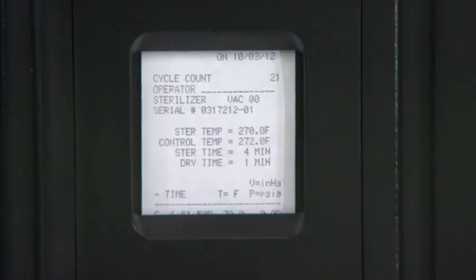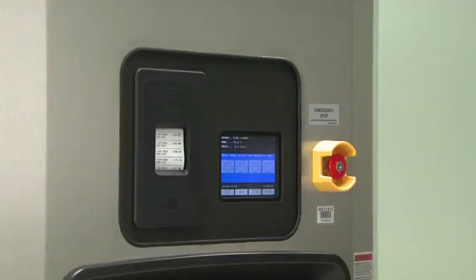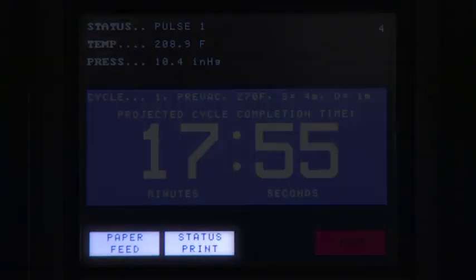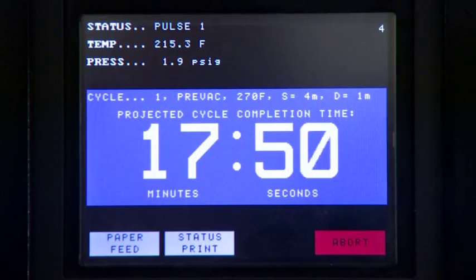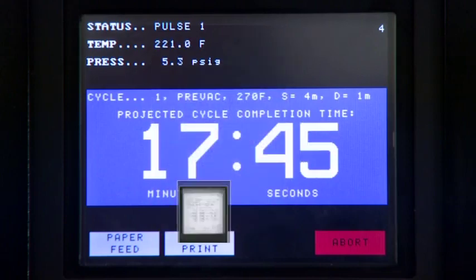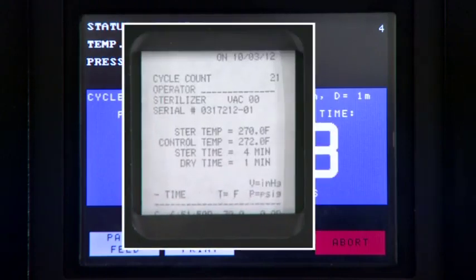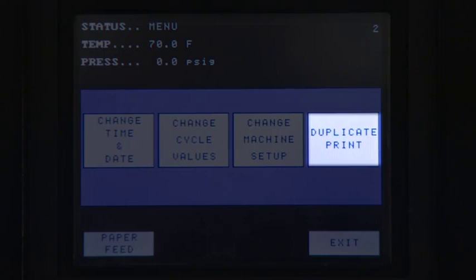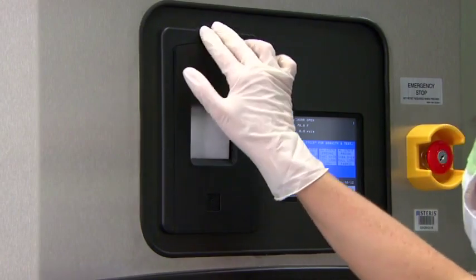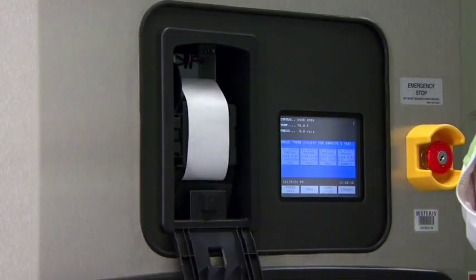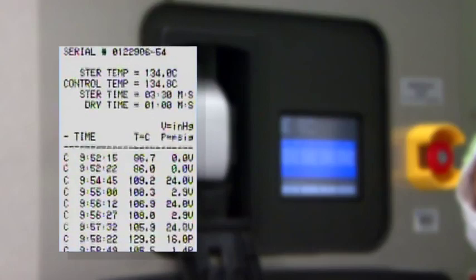The printer, which records all cycle data, is found next to the control panel. Its function buttons can be found on the control panel's typical in-cycle screen. Options include paper feed, which you would press to feed out paper from the roll stored inside the control; status print, which provides a printout of the current cycle phase and conditions; and duplicate print, which prints out the last previously run cycle. The procedure for changing the paper will be covered with routine maintenance later in the video. Reference the operator manual for information about interpreting the status print codes on a cycle printout.